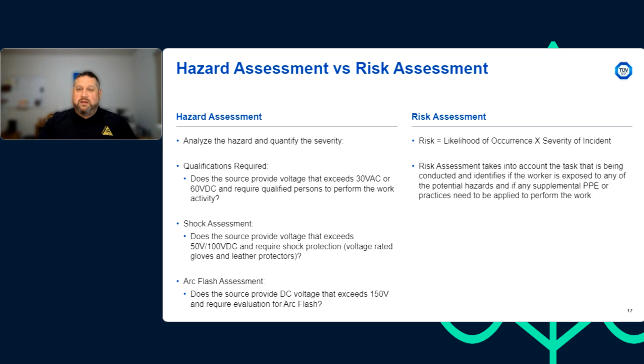Some of the elements of a risk assessment procedure would be identifying the hazards - this is really directives from NFPA 70E specifically. We need to assess the risks, implement risk controls according to the hierarchy of risk control methods, validate the effectiveness of the risk control measures taken, and then document. This is one of the things I see a lot of employers currently missing right now: proper documentation of your risk assessment.